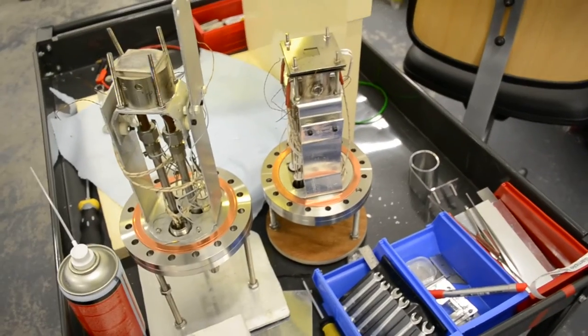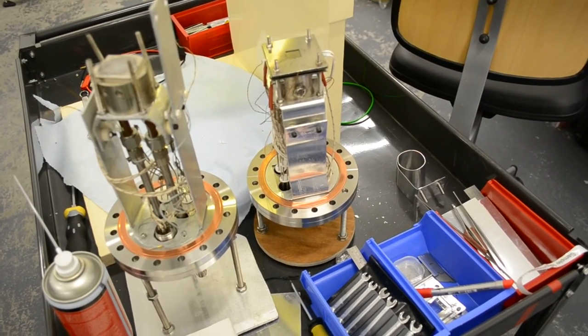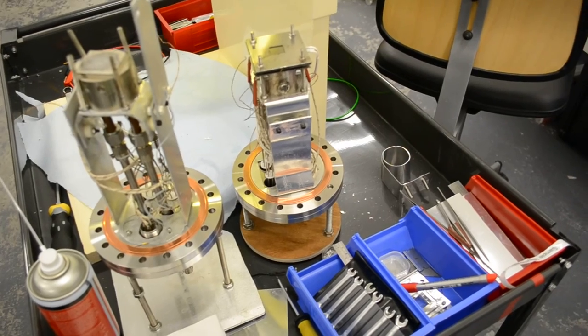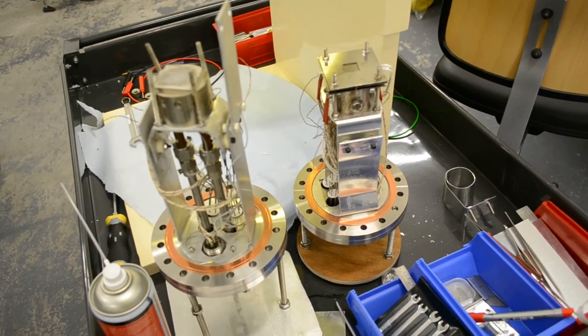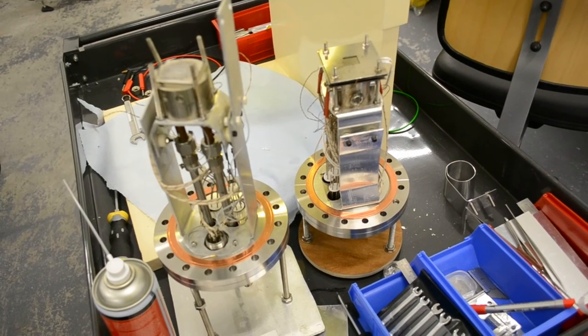This is the chamber where the stage with the sample is to be mounted, the end of the beam line. Here is the stage. The sample will be mounted through this tantalum shield. The scanning area can be from 0.5 to 6 cm square.